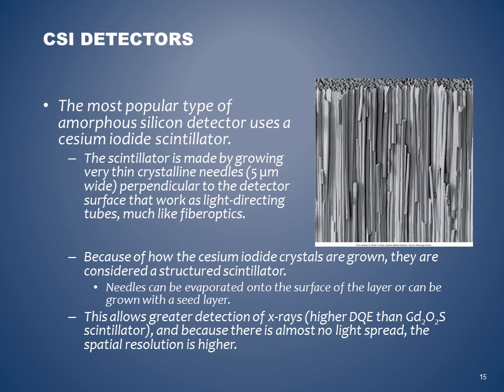CsI detectors. The most popular type of amorphous silicon detector uses a cesium iodide scintillator. The scintillator is made by growing very thin crystalline needles perpendicular to the detector surface that work as light directing tubes, much like fiber optics. And when you're looking at the image to your right, you can kind of see how that would remind you of fiber optics. Because of how the cesium iodide crystals are grown, they are considered a structured scintillator. Needles can be evaporated onto the surface of the layer or can be grown with a seed layer. This allows greater detection of X-rays, so higher DQE than Gd2O2S scintillator, and because there is almost no light spread, the spatial resolution is higher.